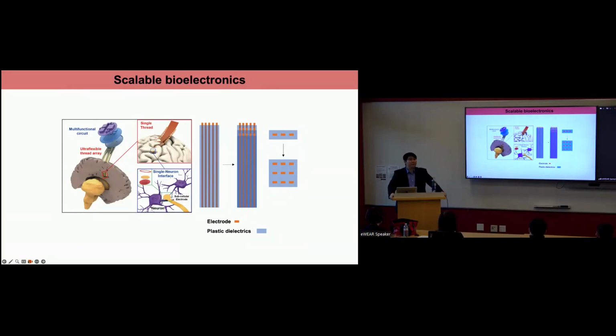However, the challenge is that those metals, those conducting materials, can be made into a very thin structure, like 20 nanometers or 40 nanometers, that is sufficient for their performance. But the dielectric layers that are used to encapsulate those conducting structures cannot be further reduced. Previously, we reduced the thickness of the probe down to 800 nanometers in total for both sides. That will be 400 nanometers on each side. That already approaches the limitations of the dielectric material.